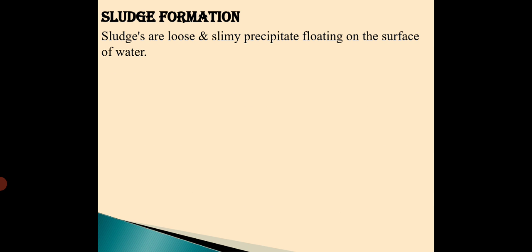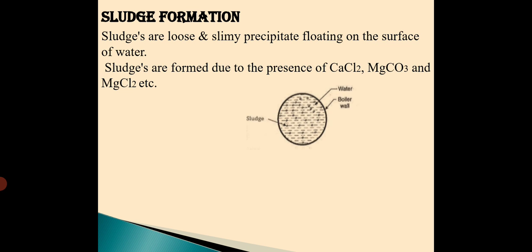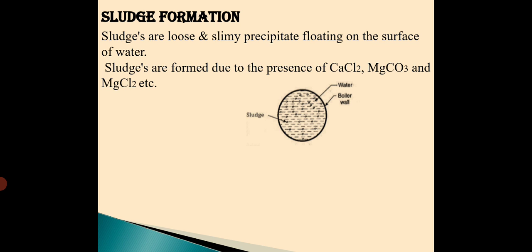The next one is sludge formation which is a very similar problem like scaling. What are sludges? Sludges are loose and slimy precipitates which are floating on the surface of water. What is the difference between these sludges and scales? Scales stick onto the inner surface of the boiler but these sludges will be floating on the surface of water. This is the only difference. These sludges are formed due to the presence of calcium chloride, magnesium carbonate, and magnesium chloride. This image shows the floating of sludges on the surface of water inside the boiler.